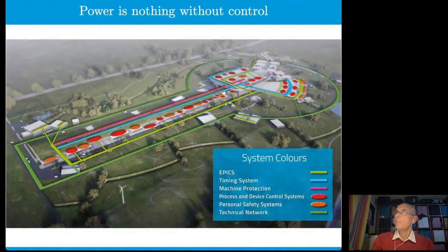And our control, this is our site from the top, is divided in several layers. Let's say from quite fast control that is based on FPGA, and is there to protect the machine, basically. We have even another control that is for personal safety, but that one is separate from all of these. The FPGA is to protect the machine because the beam goes at the speed of light. I don't have to tell you, most of you are particle physicists, so you know. And so we need a very quick system to protect the accelerator if we have some loss, if we lose the superconductivity, or if we have some other issue. Then there is a slow control system that is the one used by the operators, and mainly our Python coding goes there.